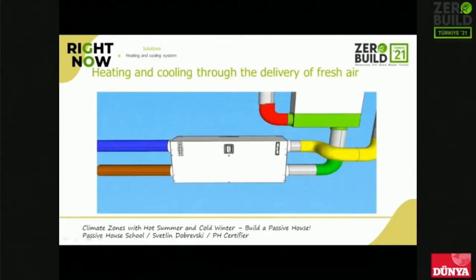The last challenge that had to be solved was heating and cooling systems. The results in the PHPP have shown that the heating and cooling demand covered the certification criteria, but the heating and cooling loads were still too high for having the possibility for heating and cooling through the delivery of fresh air. It was a problem because it seemed that one of the main advantages of the passive house concept could not be used. In such cases, two approaches are usually used.